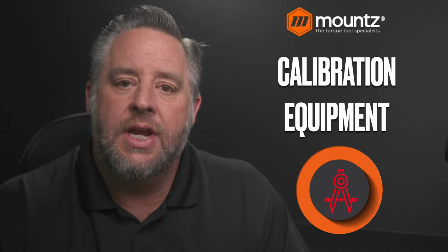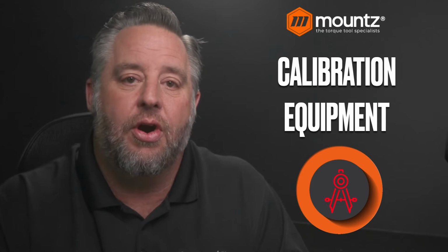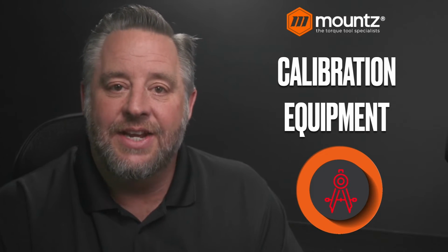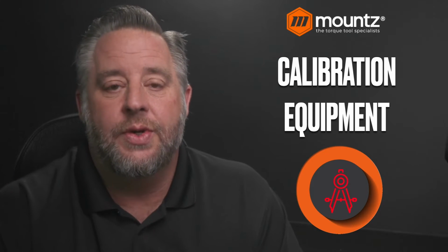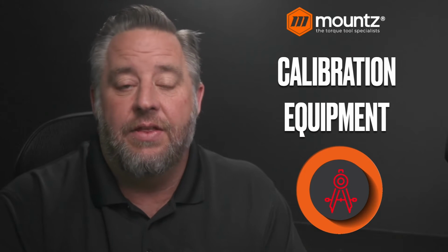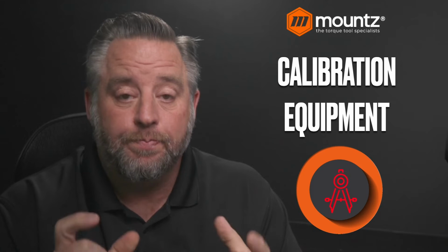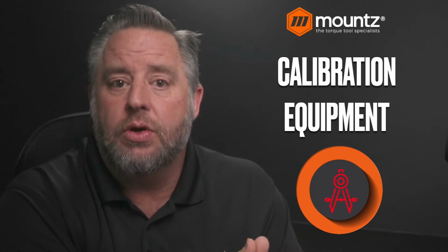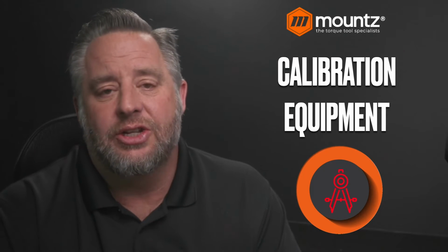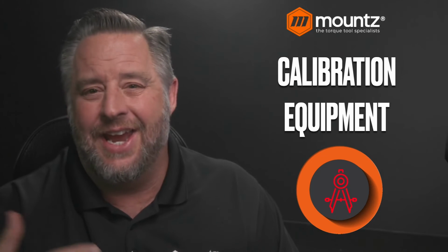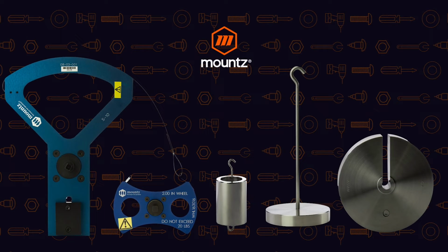Not only is the strain gauge part of it, but there is also additional equipment that needs to be purchased or used when we're doing a calibration of the analyzer. When we take a look at what torque equals, it's distance times force. So we use specially designed segment arms and weights. These are all traceable to NIST, and all of the weights are Class F certified. We have our wheels and segment arms, which provide the distance in the torque relationship, and then the weights provide, obviously, our force.